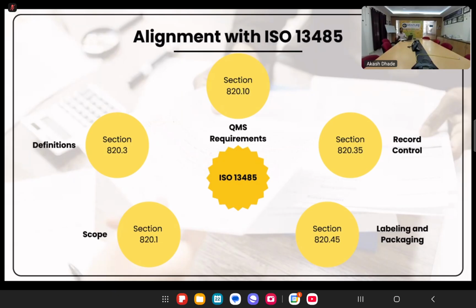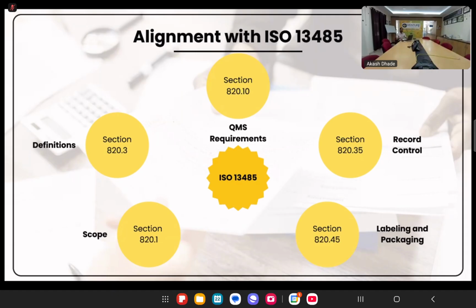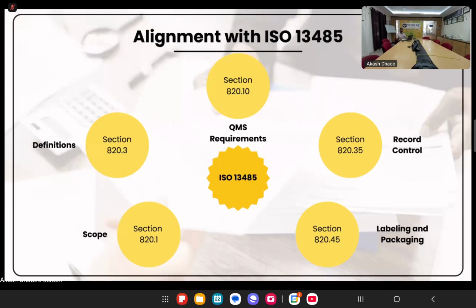How many members were involved? What was their qualification? This was recorded. When the root cause analysis is done, then what was the CAPA that was initiated? What was the corrective action? So you will document or record that corrective action in place. Okay. Once that corrective action was recorded, you will implement that change in your design or in your QMS. So that should also be recorded. So section 820.35 talks about this record control, and it is also in alignment with ISO 13485. So whatever activities you are conducting or executing, you should have a record of those activities. So 820.35 talks about those record control activities.